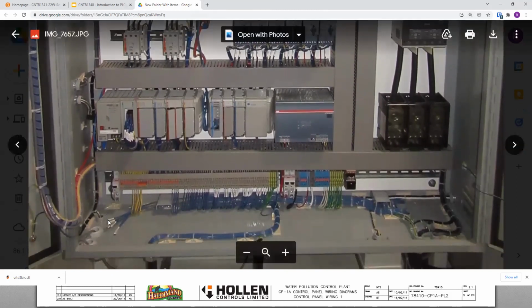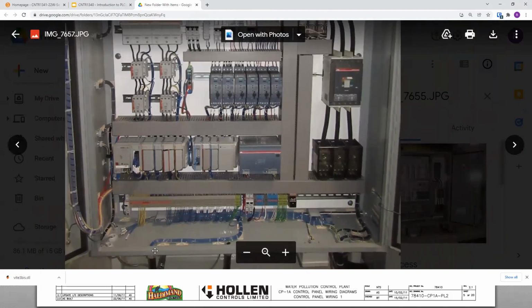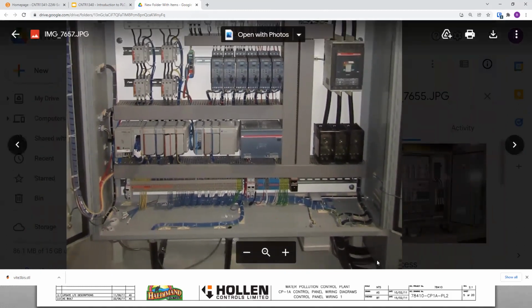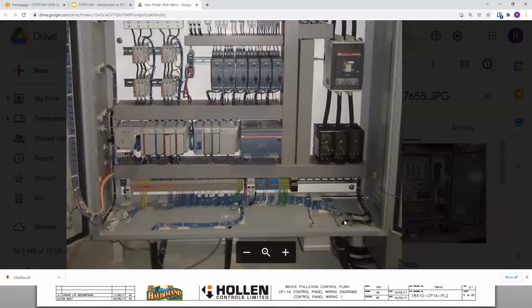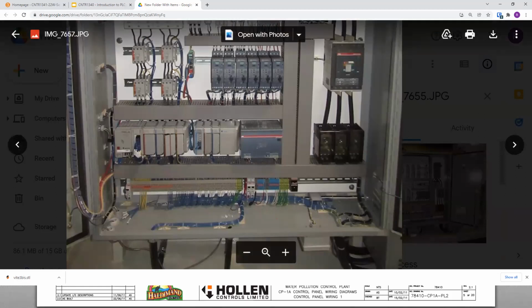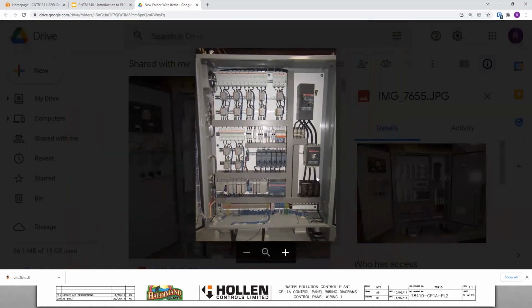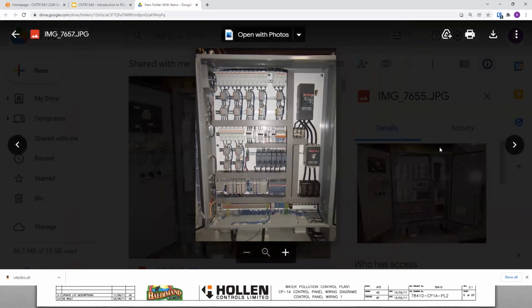Yeah, so you can see here your field IO, or the stuff that's coming from your skids, coming up through the bottom of the panel. This is going to be your terminal blocks to connect up to your IO, probably some signals up in here as well. Is this 600? 340? I think this was 480. 480? Yeah.